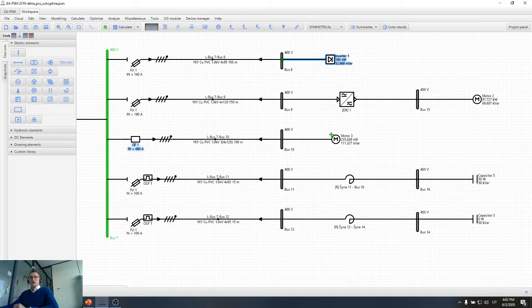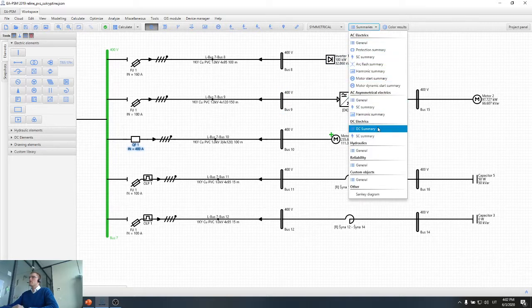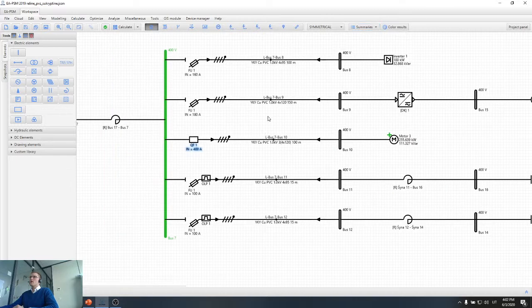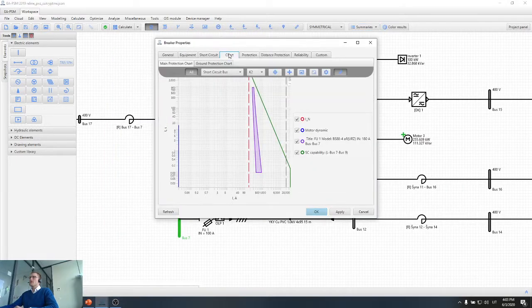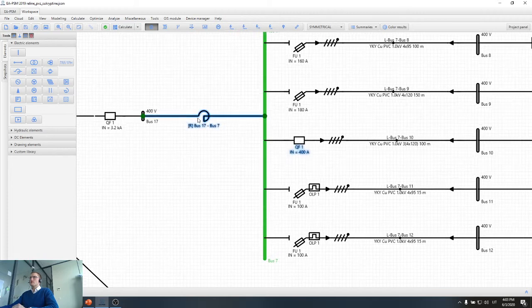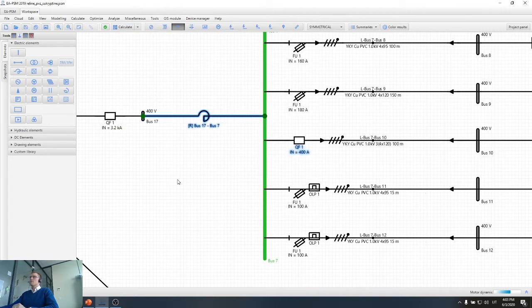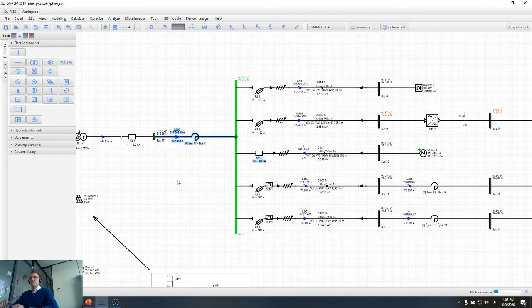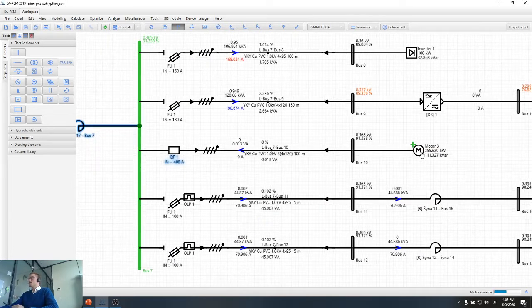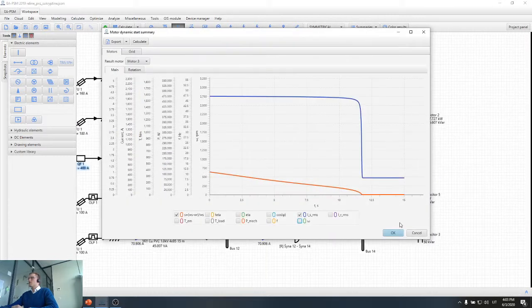So the next question was, while doing motor starting analysis, why not consider transient voltage dip parameters? When we do motor starting analysis, the software automatically evaluates the voltage dip in the network. For example, let's calculate motor starting one more time, because I changed the network a little bit. I added this reactor here. So let's calculate motor start dynamics one more time. The software automatically evaluates the voltage dip which is created during motor starting.